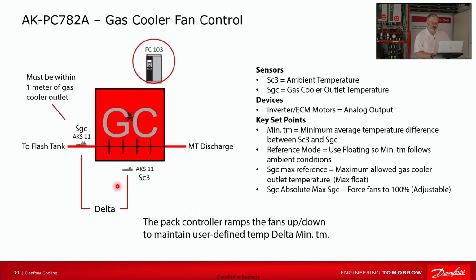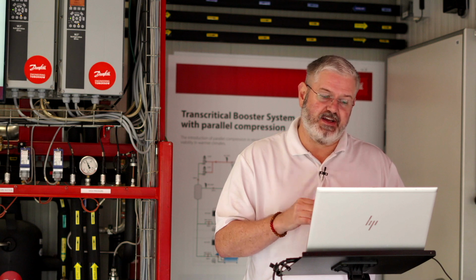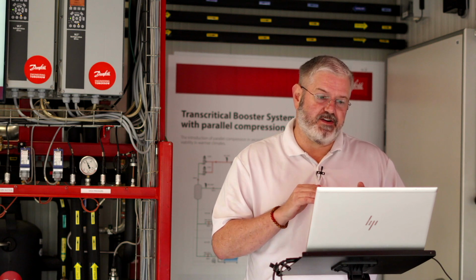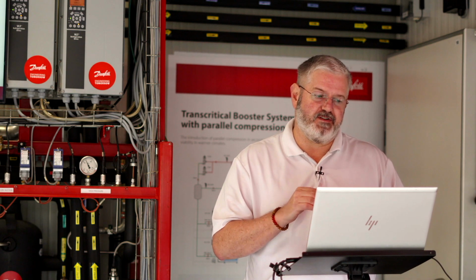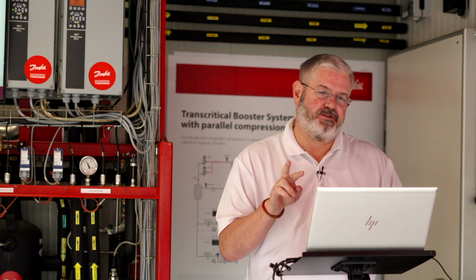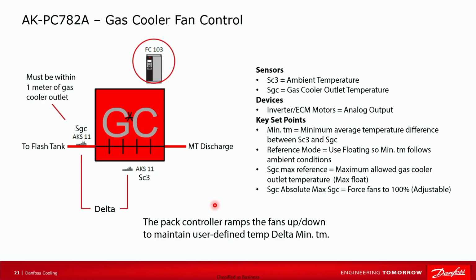One other quick note on the temperature sensors, these get reversed pretty often. And what that causes is the ambient would be reading a higher temp than what it thinks is the outlet down here. So it basically never turns the fans on. It would make the gas cooler think that it's cooler than it actually is. So if you're struggling at a startup or in the field to get fans to turn on, decent chance that those two sensors got reversed.